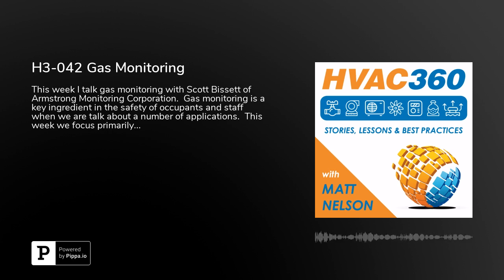What we typically do is take advantage of the accuracy of the new infrared sensors, and we try to alarm at the lowest reasonable level. The reason is that refrigerant is an expensive product, so we want to catch a leak as early as possible. We want to protect not only the personnel that could potentially be working in the space, but also the investment of the building owner or operator, who has a bunch of money sunk into the refrigerant in their chillers.